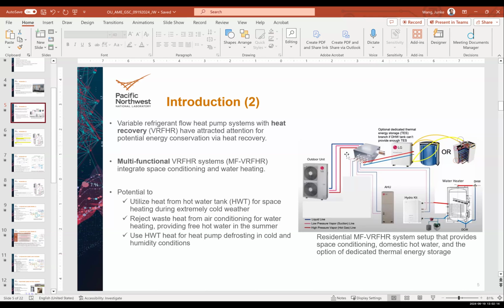Even currently, with these two, either heating or cooling, we find that this is already very complicated. I spent a few months to get a solution: how can we withdraw heat from the tank? Because the baseline control, like the out-of-the-box control, this system did not have this ability. This system can only run either heating or cooling, or AHU in cooling with tank in heating. That's only three modes. Because now we want to run the tank in cooling, right? So you are able to draw the hot water from the tank.